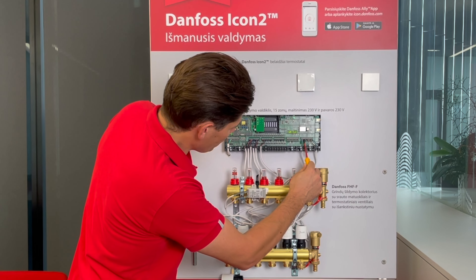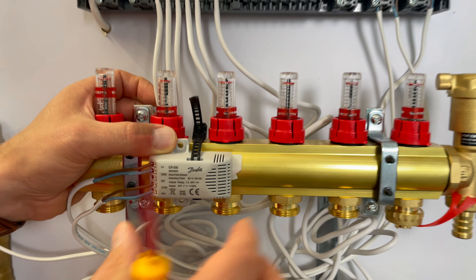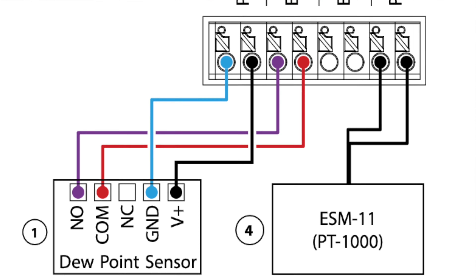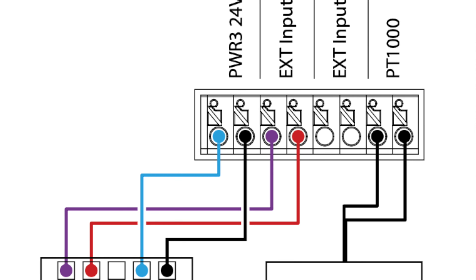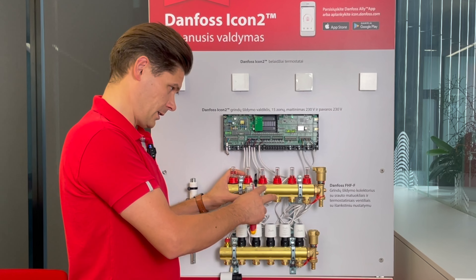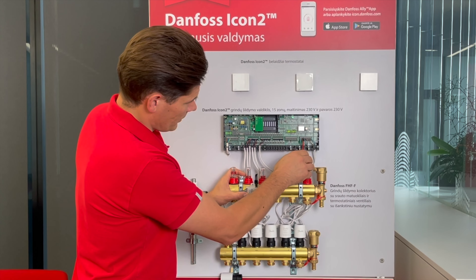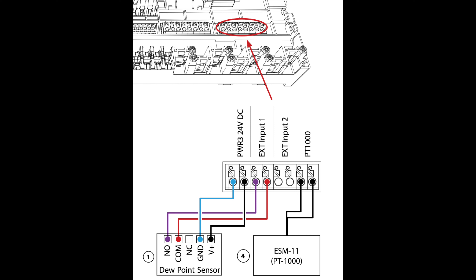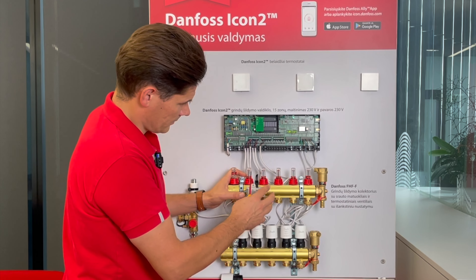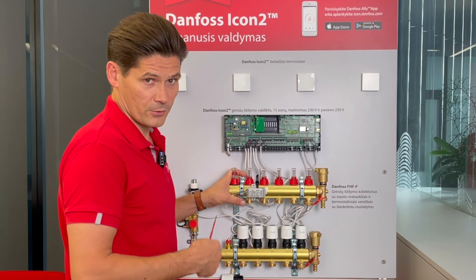The last inputs are for the dew point sensor. The dew point sensor detects moisture on the manifold in case you have underfloor cooling — you wouldn't want condensation on your floor. The first point that starts condensating is the manifold, so we measure moisture there. If moisture is detected, the sensor sends a signal to the controller to temporarily stop underfloor cooling, wait until the moisture goes away, then automatically restart the cooling procedure.